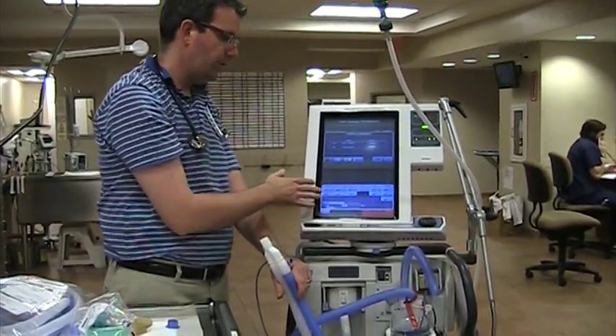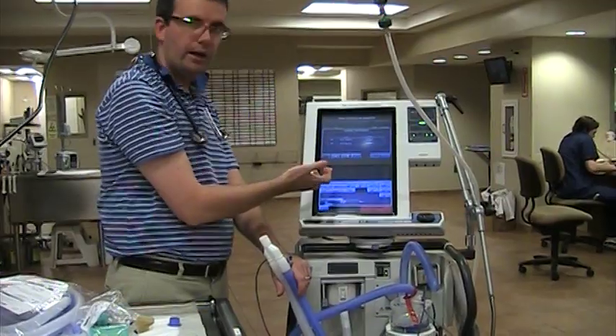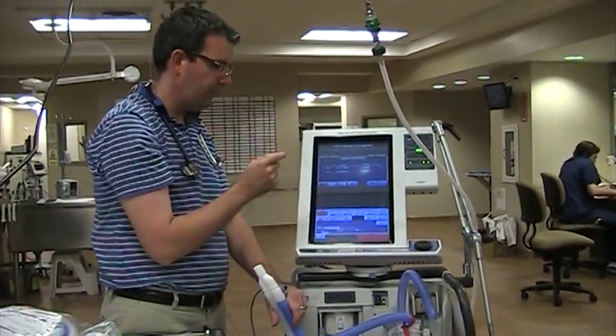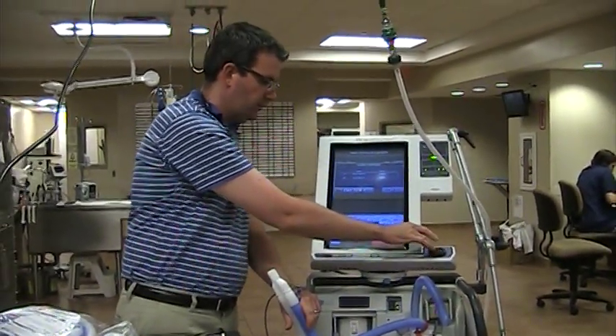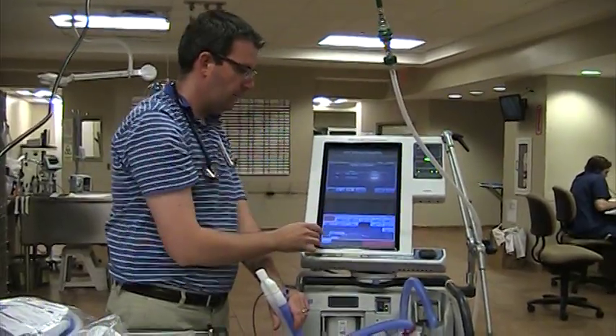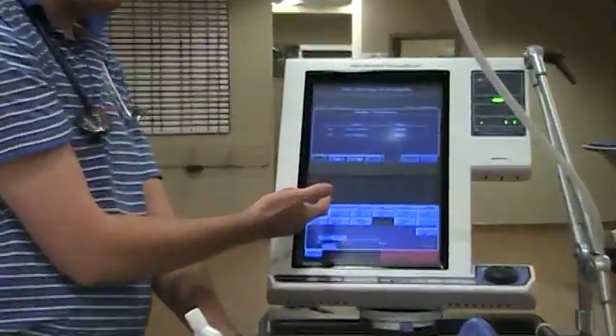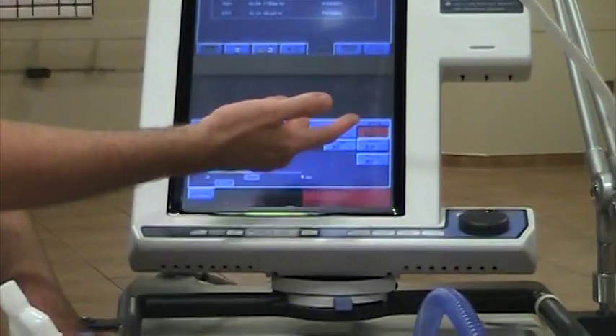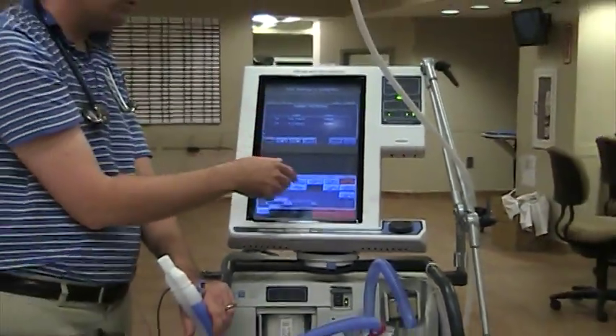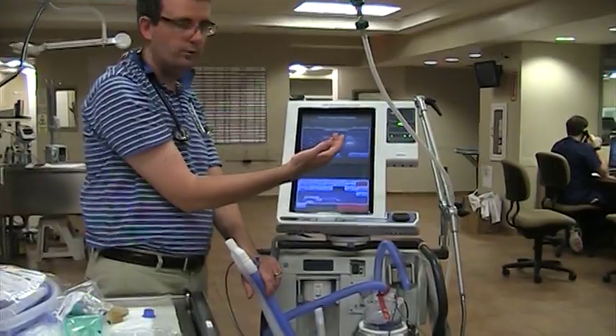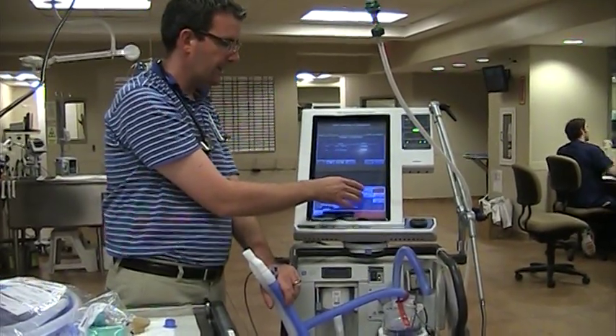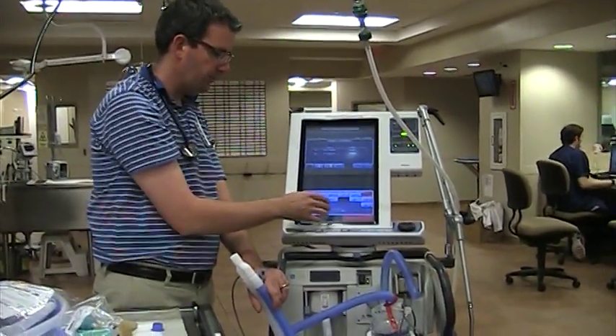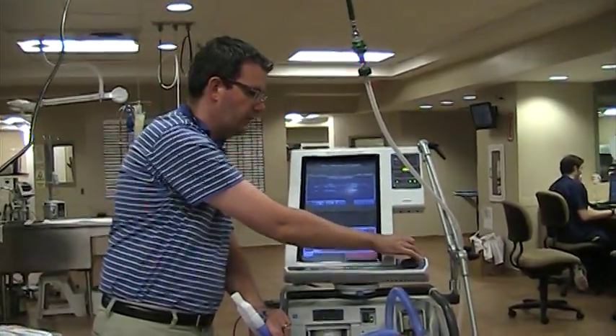So it comes to this screen right here. If we want to change the number of breaths, we press the F button and change the number of breaths. Because we chose volume control, we can choose the total volume by pressing VT. We want to have the FiO2 at 100% to begin with. The PEEP will vary according to whether there is lung disease or no lung disease, but it can range up to 20 centimeters of water. And then everything else is pretty much the same. So once you're ready to go, you then press accept.